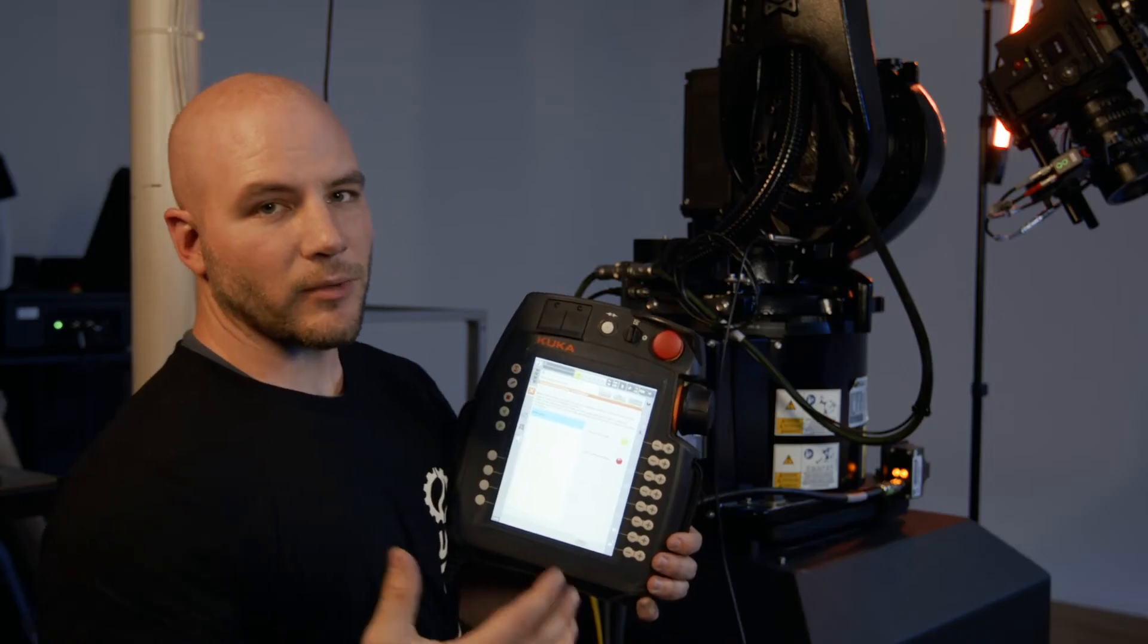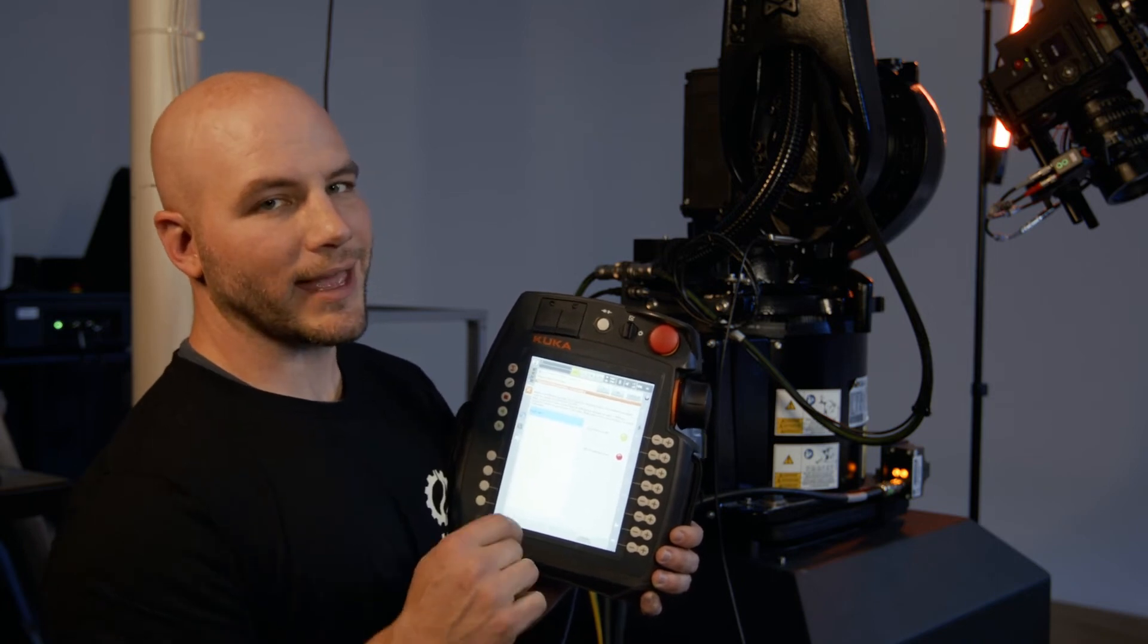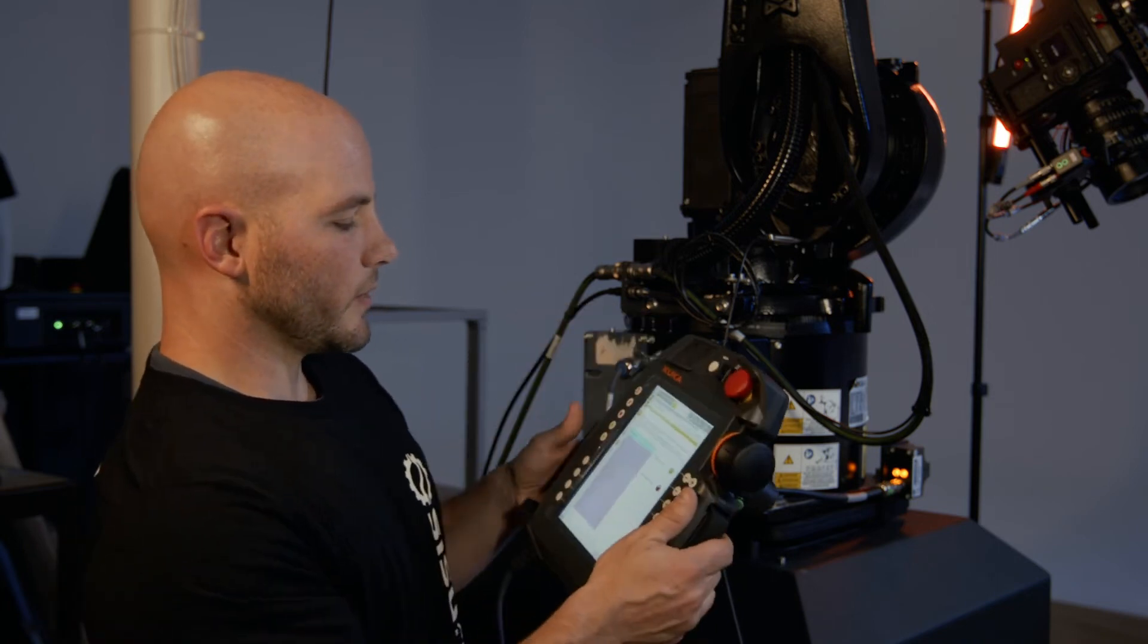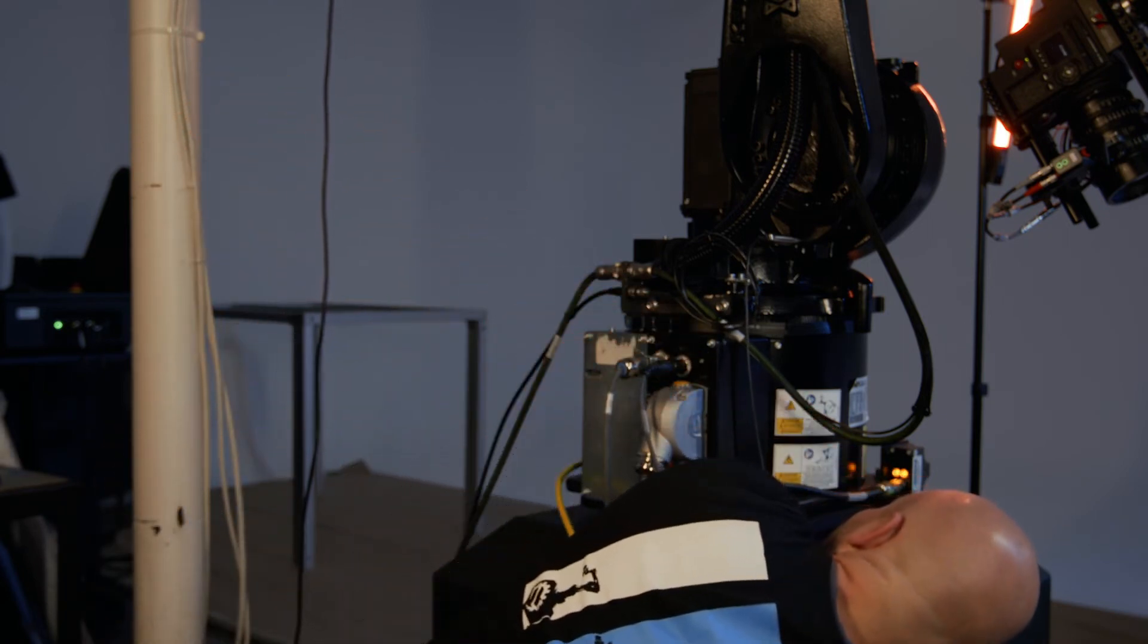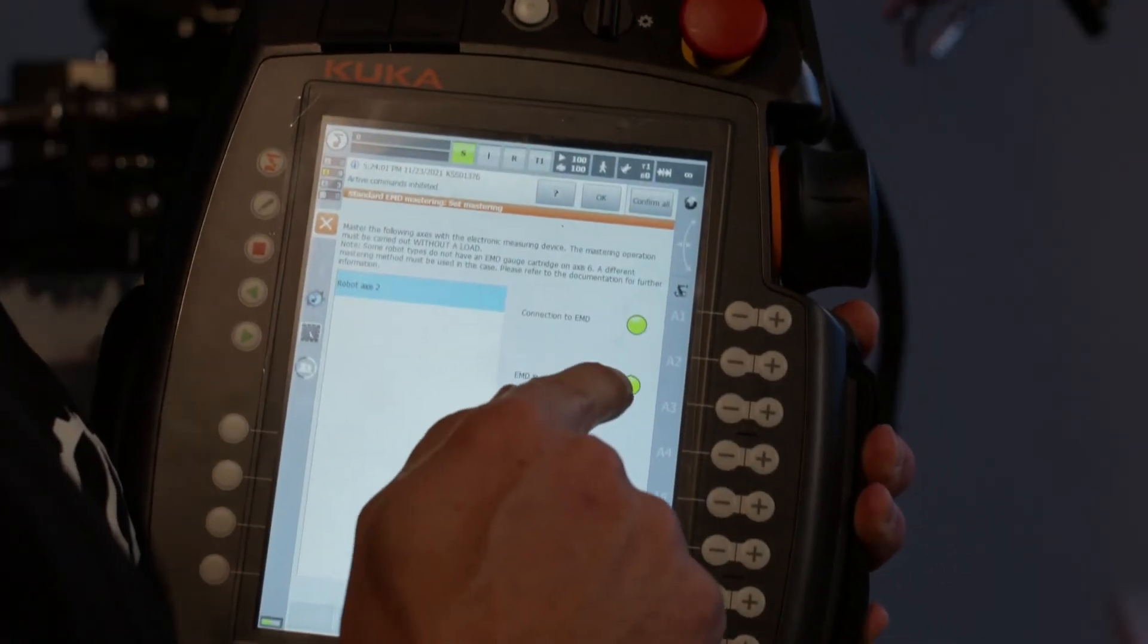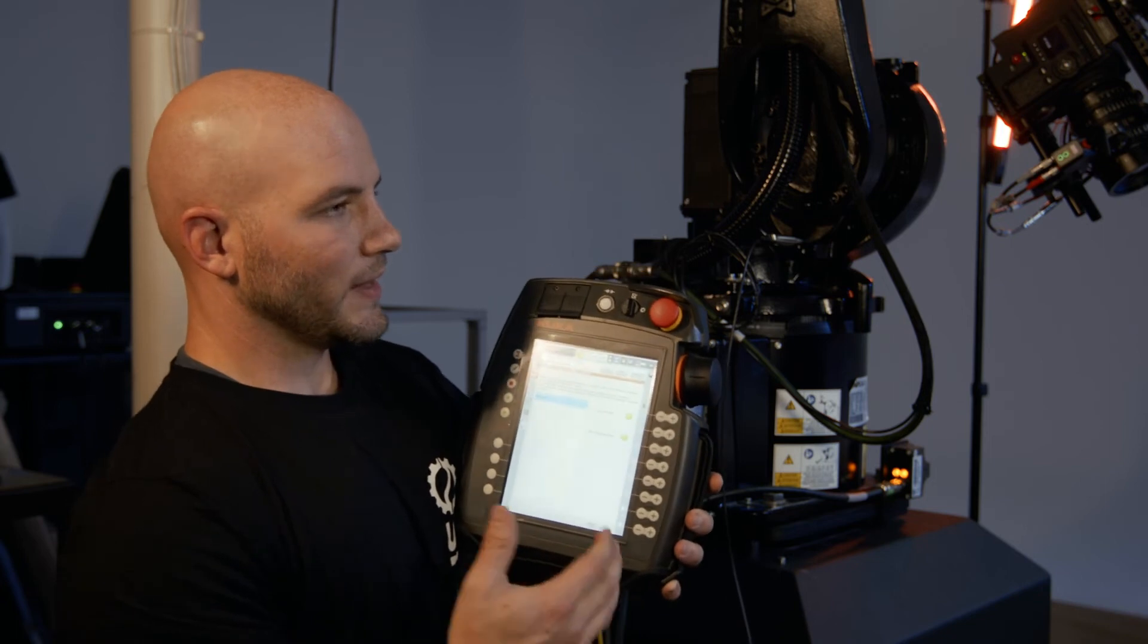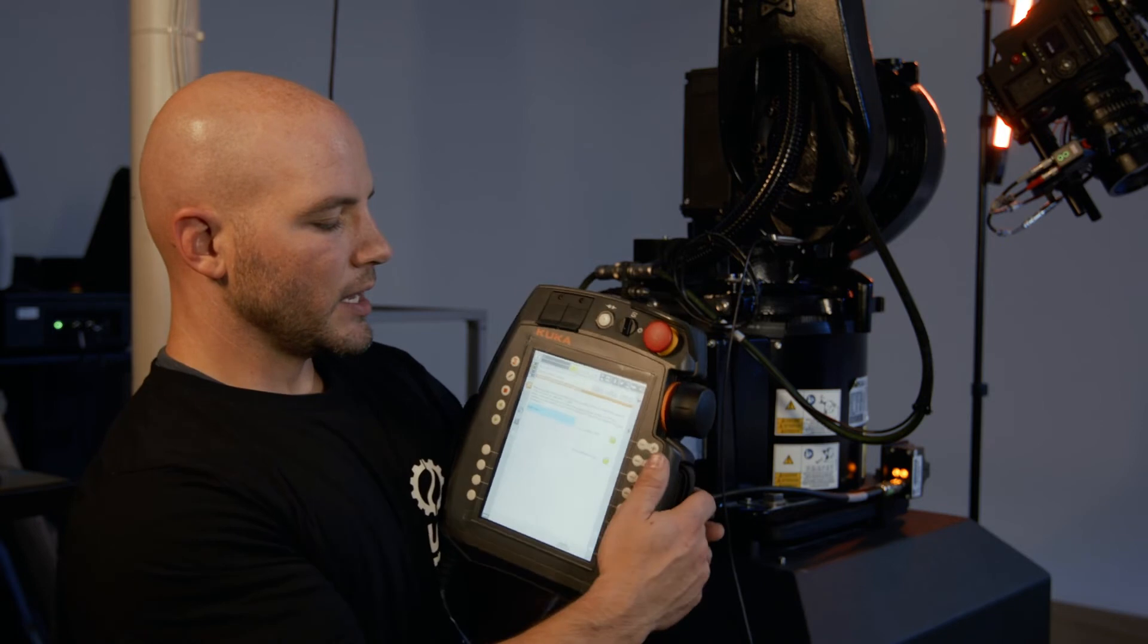So now what I want to do is I want to move that probe until it's right in the valley of that groove. So what I'm going to do, I use the enable and I use the plus and minus buttons until I'm right on. All right. That looks pretty good. You'll see that this light went green. That means that it is in range. The probe depth is in range to begin the test.